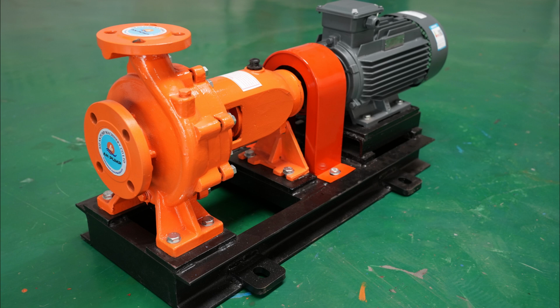What about when a pump's just using a ton of energy? Yes, that's nobody's friend. Oftentimes that comes down to it operating far from its best efficiency point, the BEP. Imagine a graph of pump efficiency: the BEP is the peak, where it's running most smoothly, using the least amount of energy. Okay, so we want to be at that sweet spot.